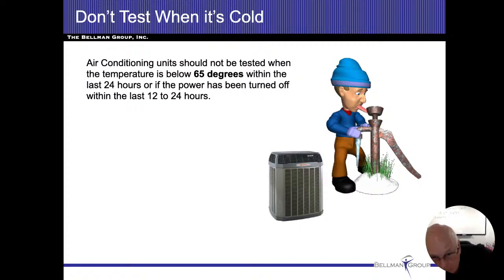It's a common practice that we do. So I'm going to ask that you don't test air conditioners below a certain temperature, and whatever number you want to choose is up to you. We're going to throw out a very conservative, safe number of 65 degrees. So at this time of year, not until April probably, will we be testing air conditioners again. And we just have a standard disclaimer in our form.